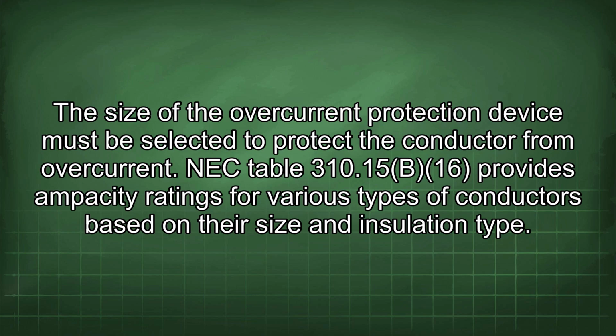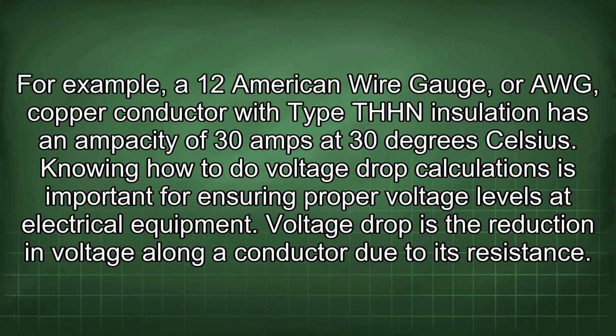NEC Table 310.15(B)(16) provides ampacity ratings for various types of conductors based on their size and insulation type. For example, a 12 American wire gauge, or AWG, copper conductor with type THHN insulation has an ampacity of 30 amps at 30 degrees Celsius.